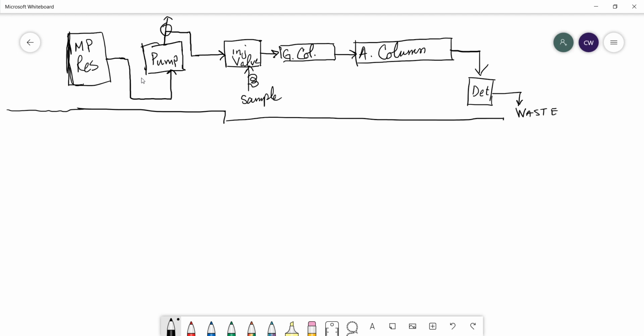Sometimes you assist it with a syringe, because once you get, especially if you have your mobile phase reservoir stored physically above the pump in the instrumentation, which I will show you in a drawing later, that will create a siphon. And so your pump will continually draw. Once that first bit of priming has been established, your pump will continually draw mobile phase from the reservoirs, with them only being under atmospheric pressure. They don't need to be under external or extra helium pressure. So that varies by manufacturer. Some manufacturers have degassing units built right into the back of the pump. So before the mobile phase even reaches the pump, there's a degassing unit that it goes through. Some don't, and you have to buy an external mechanical degasser. It really is variable based on the instrumentation and the manufacturer of it.